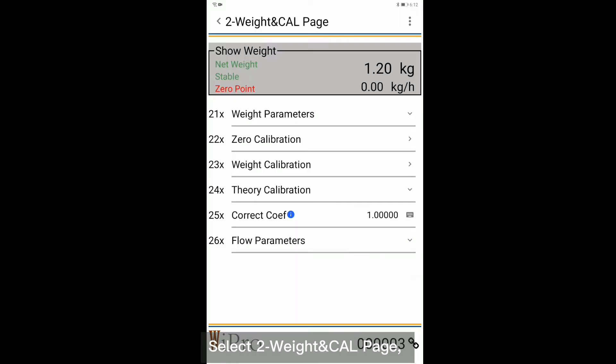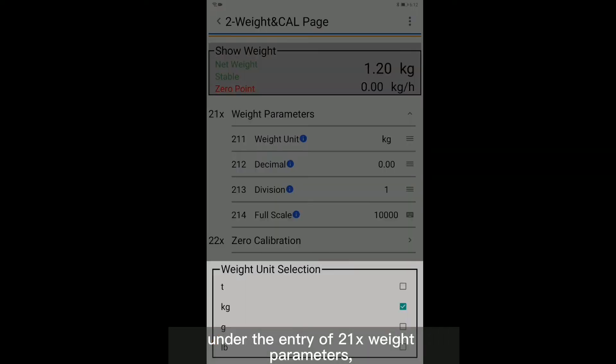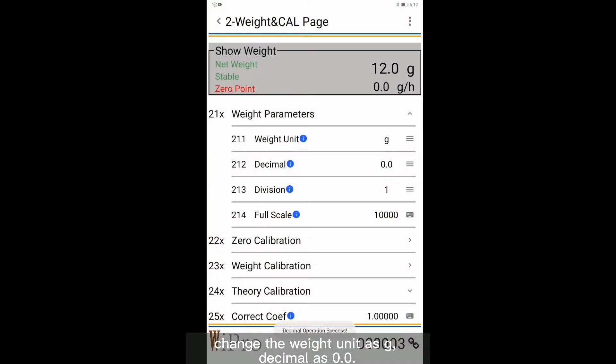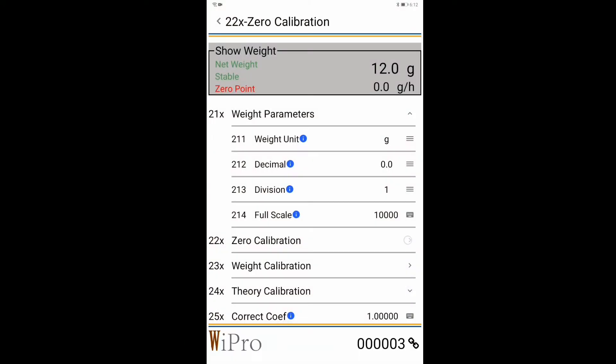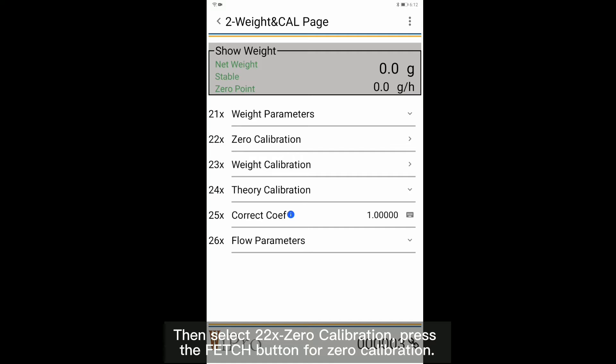Select the two-weight calibration page under entry 21x weight parameter. Change the weight unit to gram and decimal to 0.0. Select 22x Zero Calibration, then press the Fetch button for zero calibration.